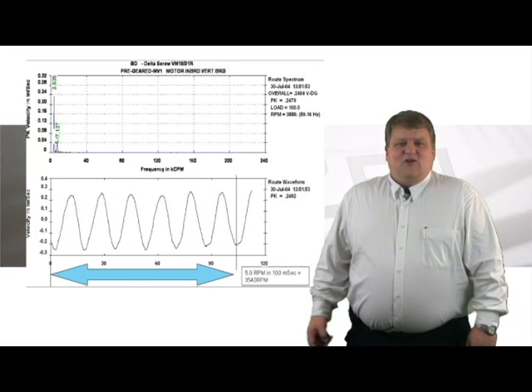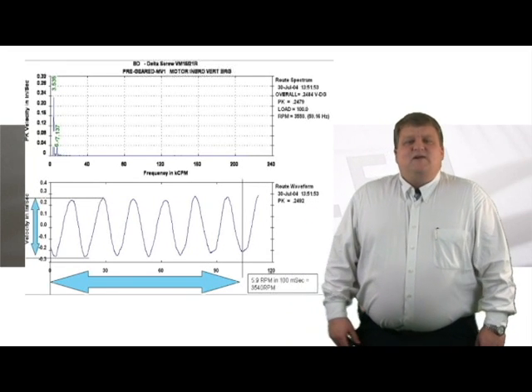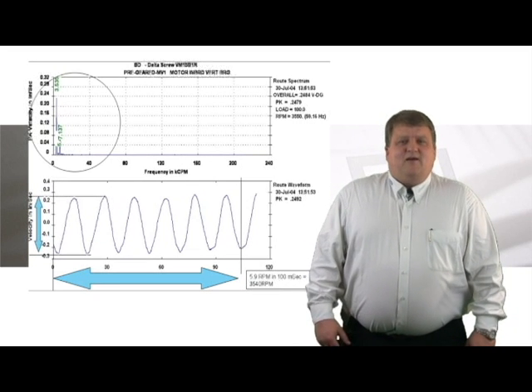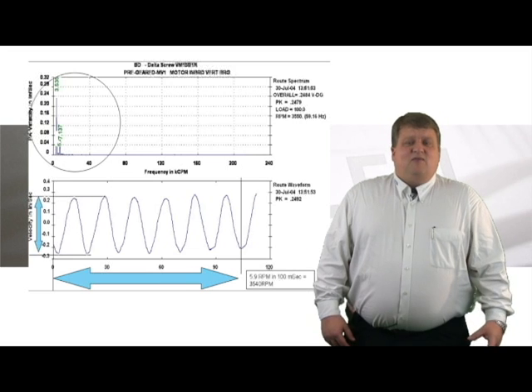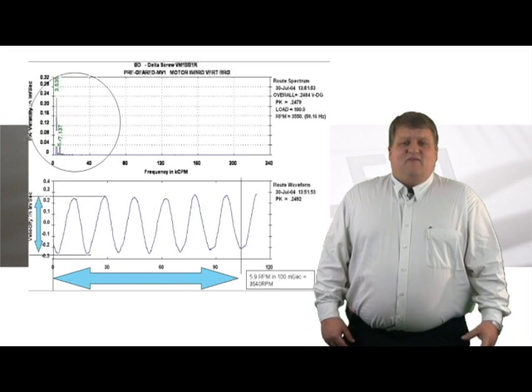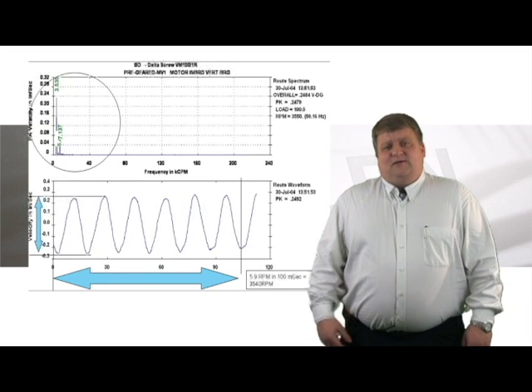The severity of it all, which is right here, that is something we're tracking up on top, right there, where we're tracking the severity in velocity, how fast my vibration is, how fast my velocity is of the vibration source here, completely imbalanced. It's very much an imbalance.